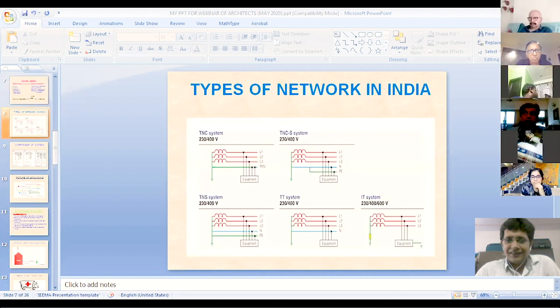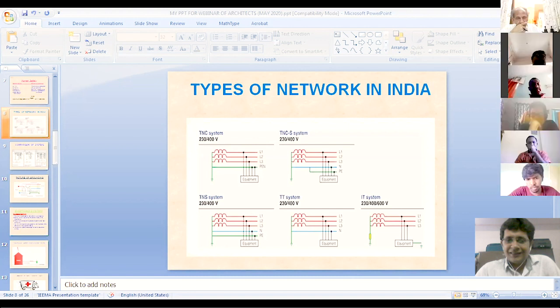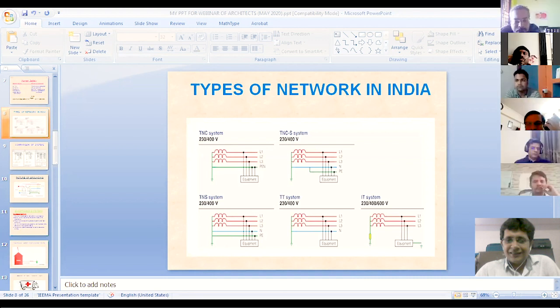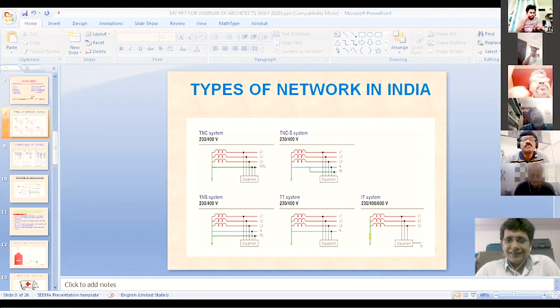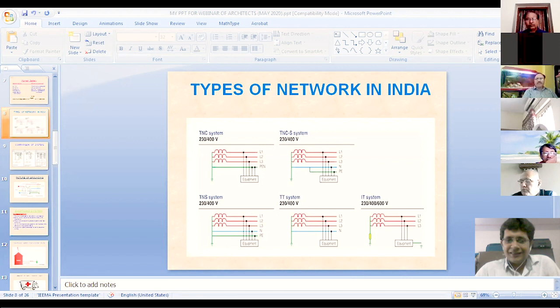You won't be anymore. We usually overlook the systems we are having. We talk about buildings and projects, but we never try to understand what kind of systems we are getting in India - it may be TNC system, TNCS, TNS, TT system, or IT system. T denotes your earthing, N for neutral, and C for combined, whereas S is for separate - when your neutral is separate and earth is separate, that becomes TNS. When it is common, it becomes TNC. IT is isolated earth, when you don't need earth. TT system is when one earthing is at the source and the second is at your project. Then there's dirty earthing and clean earthing. There is so much confusion, and you have to make yourself aware of the importance of grounding.